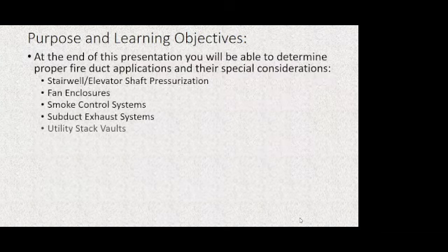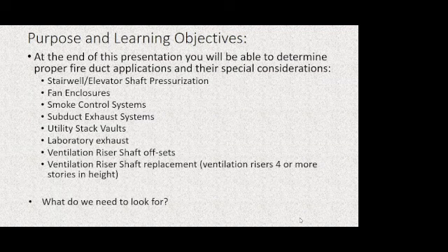You should be able to apply what you're learning here to a number of different common applications called out in the code for these kinds of fire resistance and the protection of the ductwork systems, and often the fans, power, and controls associated with these systems. We'll talk about all of that as well. Some of the most common and simple systems are stairwell and elevator shaft pressurization, when those ductwork systems are within the building envelope. Certainly, if there are inline fans in the building, they need to be in dedicated, we'll talk about that, rooms with fire resistance equal to the shafts in question.